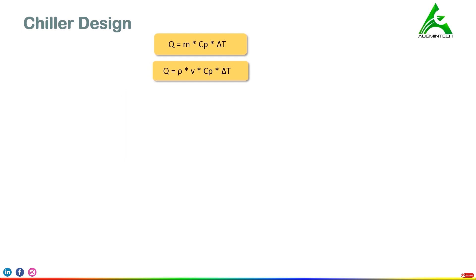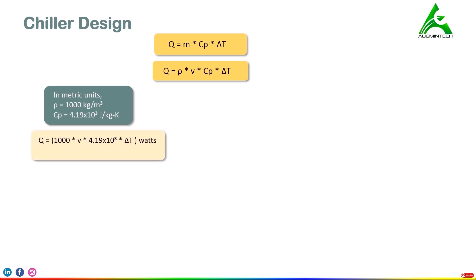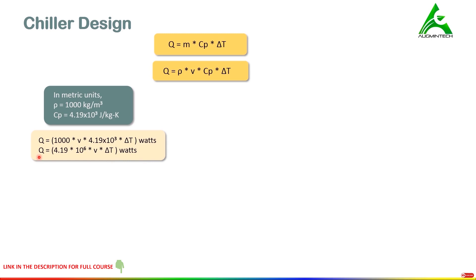Now we'll understand more details related to this equation in metric units. The density of water is 1000 kg per meter cube and the Cp value of water is 4.19 × 10³ joules per kg kelvin. Substituting rho and Cp into the main equation gives: 1000 × V × 4.19 × 10³ × delta T, with the final answer in watts (joules per second). Multiplying the constants, we get a direct formula: if we have volumetric flow rate and temperature difference in SI units, we can use this formula to calculate q.